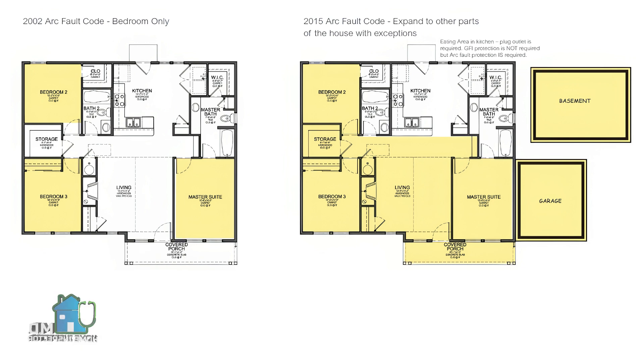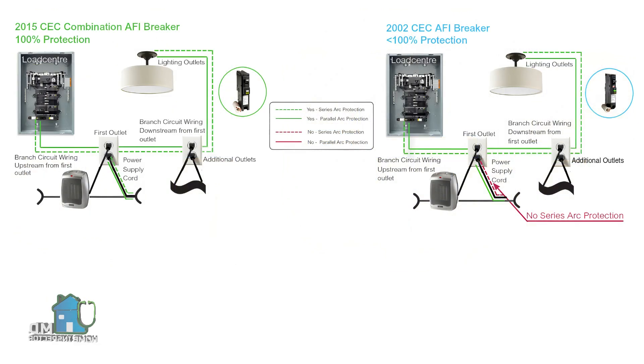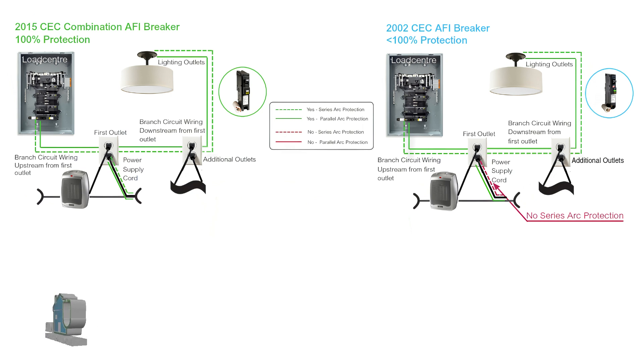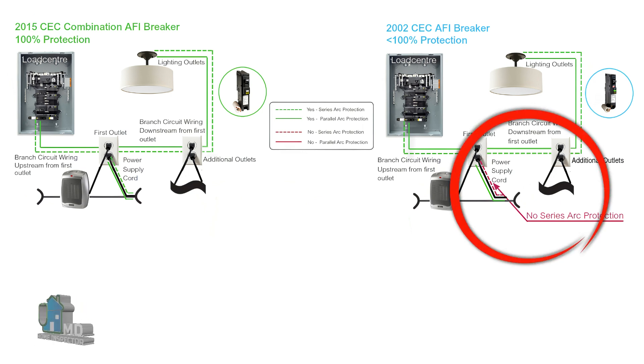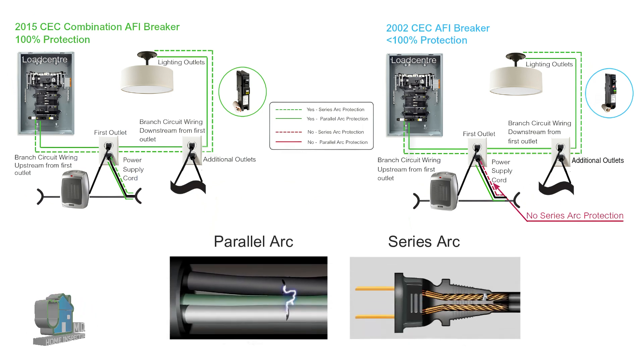A combination arc fault breaker is not an arc and people-protection ground fault breaker in one — that was confusing because such a breaker did exist but was called a dual function breaker. The main difference between the 2002 and 2015 versions is that the 2002 arc fault breaker did not protect the entire circuit, with no series protection beyond the outlet.